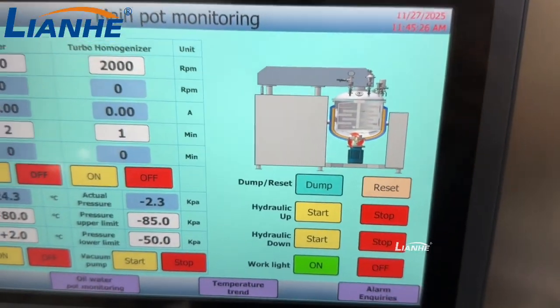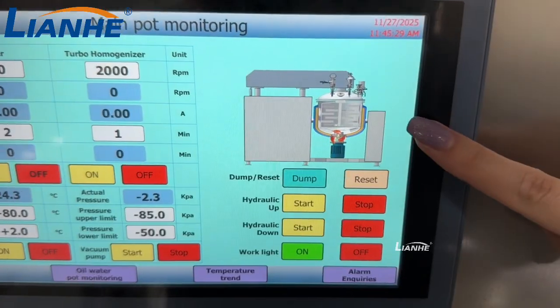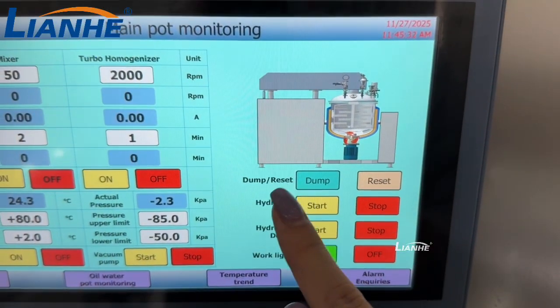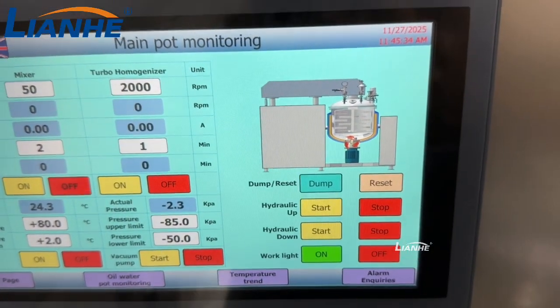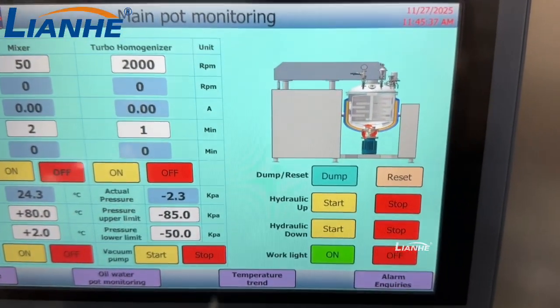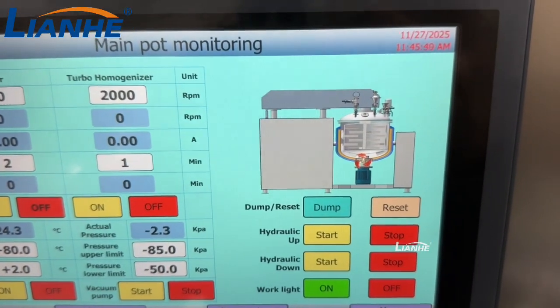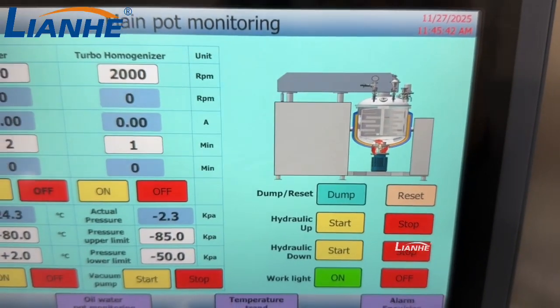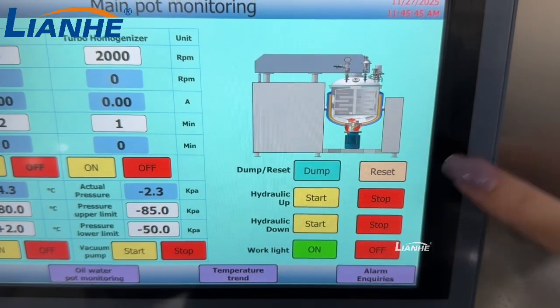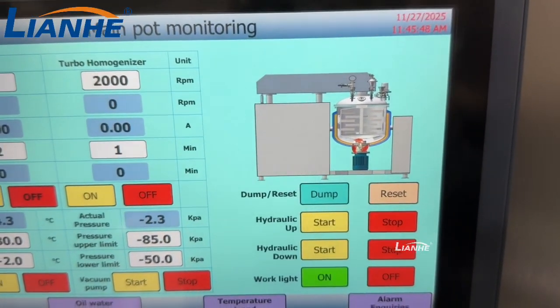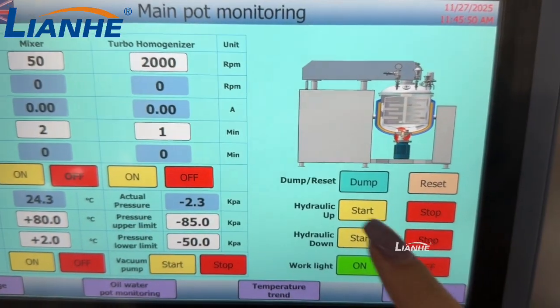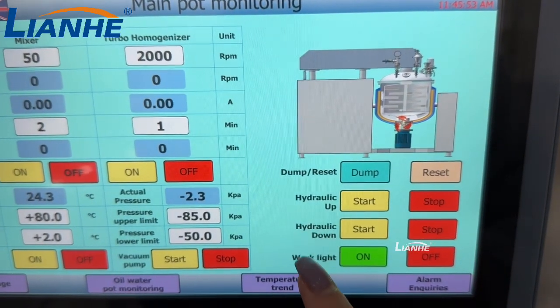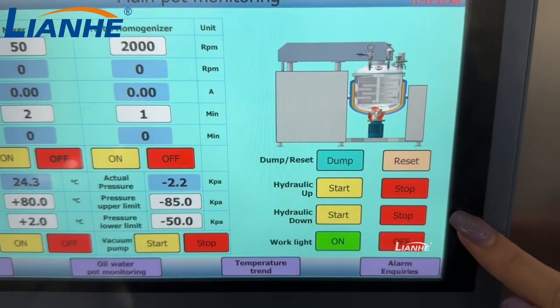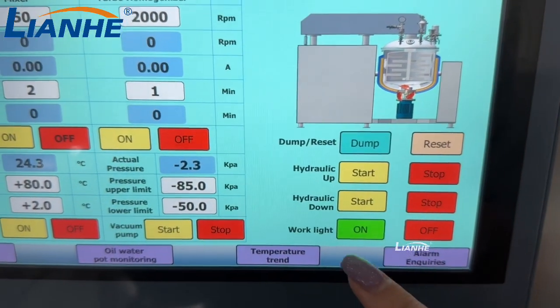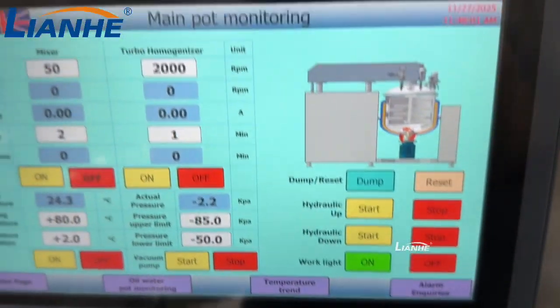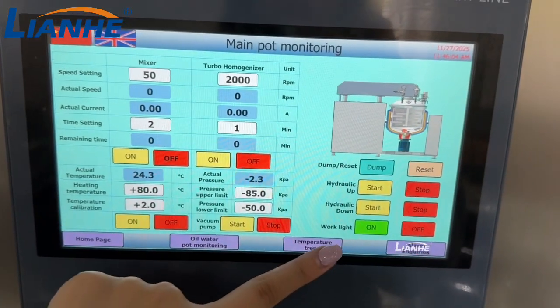And then here we can also see the diagram of the vacuum emulsifying mixer. The dump and reset means that if you want to tilt down the material, you can use the dump function. And make sure that when you use the hydraulic up and down function, you should turn on this reset button and then make sure the tank is in the correct place. And then this one is for the hydraulic up and hydraulic down start and stop function. And this work light is for turn on and turn off. And then we can check the temperature.